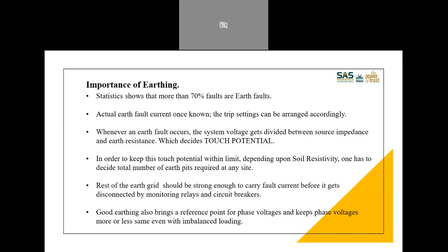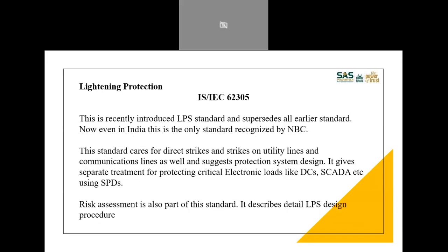We are not talking about power quality issues related to earthing in this webinar, because that's again a totally different issue. But from the safety side, at least these things have to be ensured. Now what remains is lightning protection. India had another standard till recently. Now again the standard has changed. It is IS/IEC 62305. This recently introduced LPS standard supersedes all earlier standards. Now even in India, this is the only standard recognized by NBC, the National Building Code.